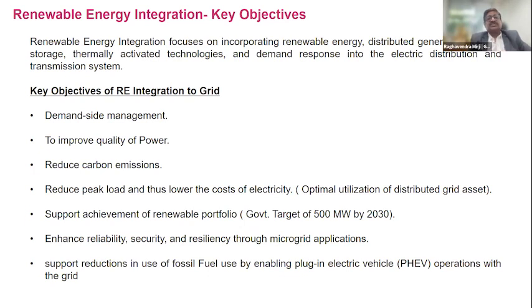The traditional systems are designed to cater to the peak load. I cannot design the entire electrical system taking care of smaller or intermediate power loads. So I need to calculate what is the peak load, and the entire system has to be designed to the peak load. If the peak load calculation goes up, the cost of the entire system also goes up. Now here I'm stating that with RE integration, the peak load will come down.